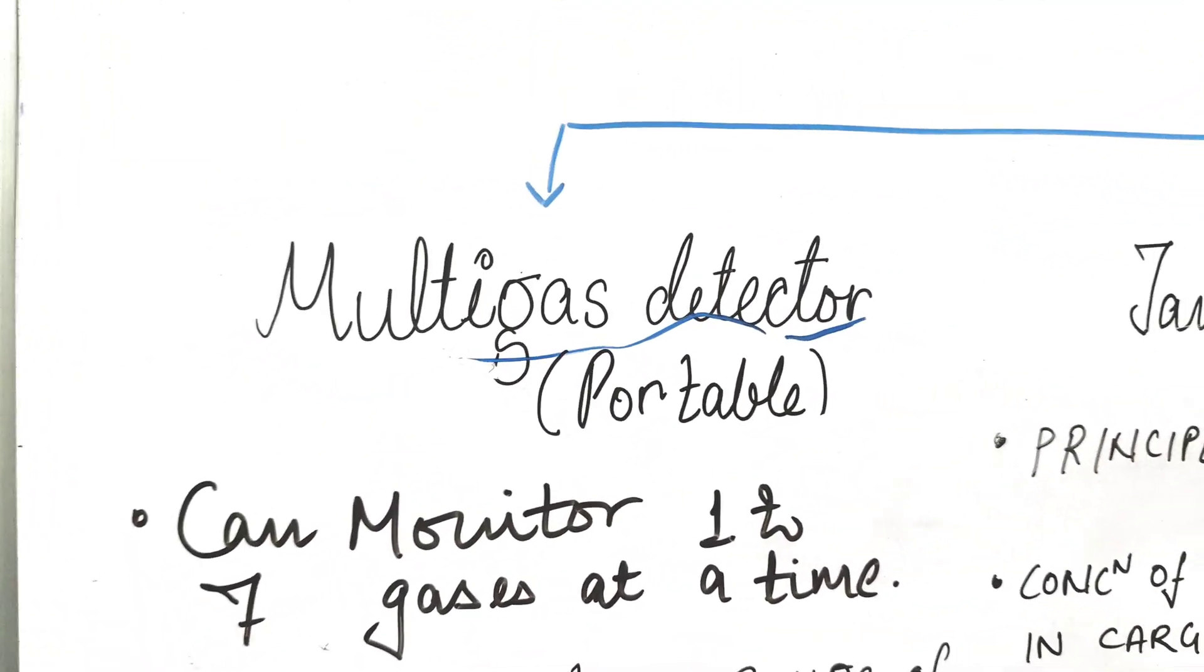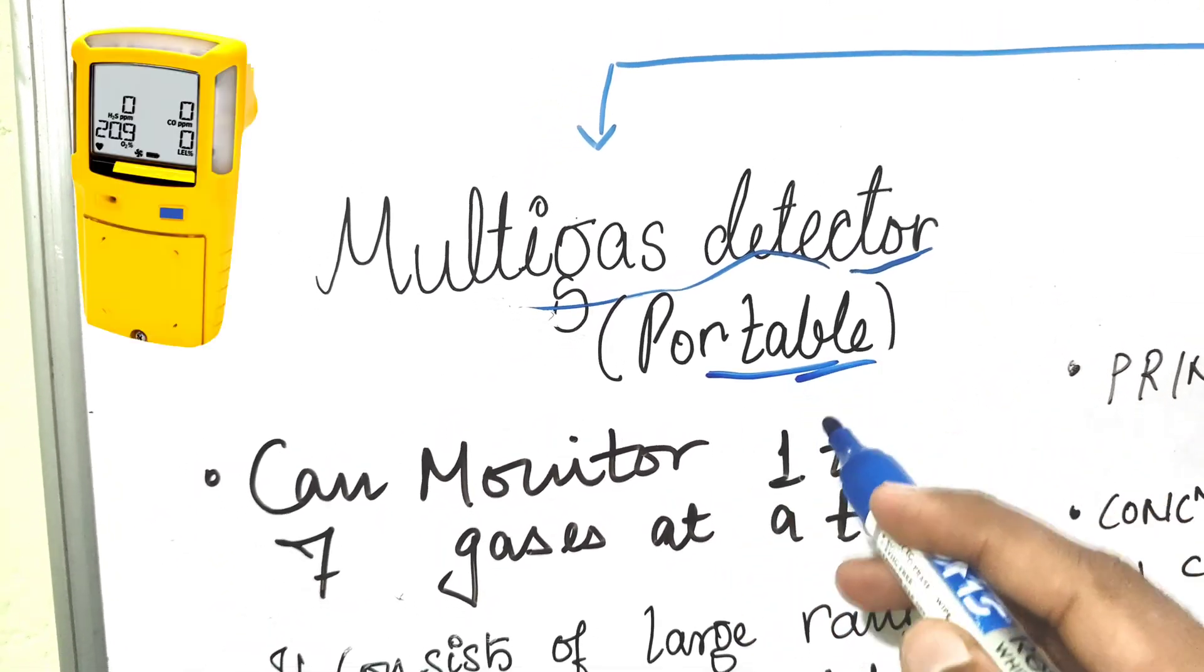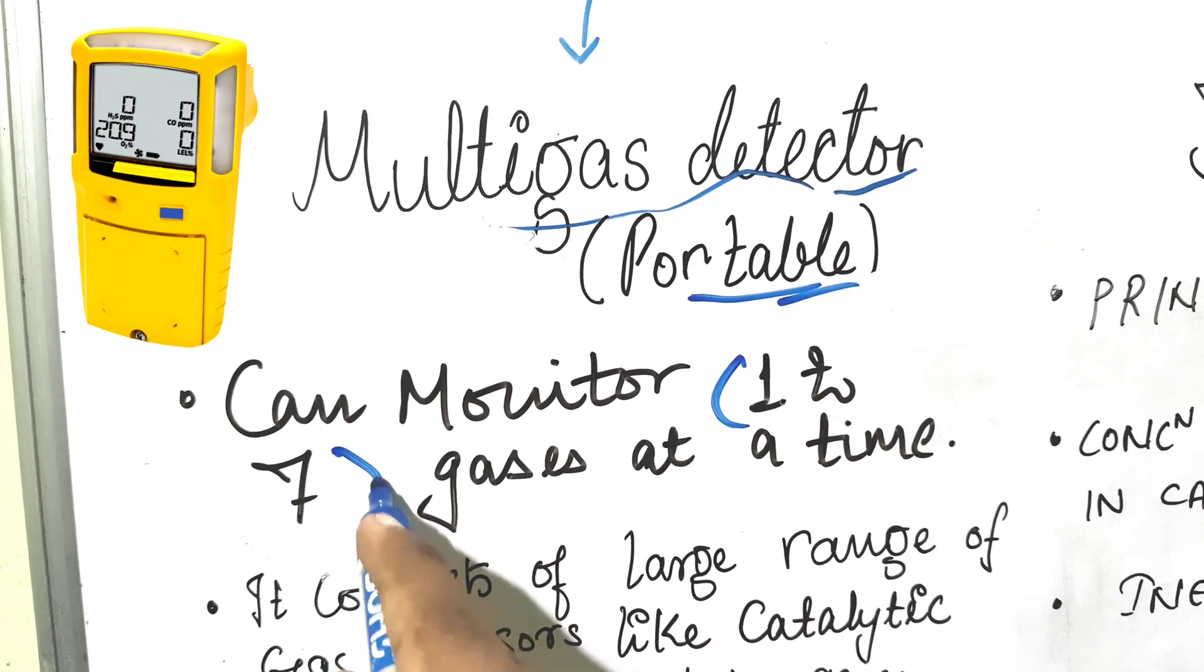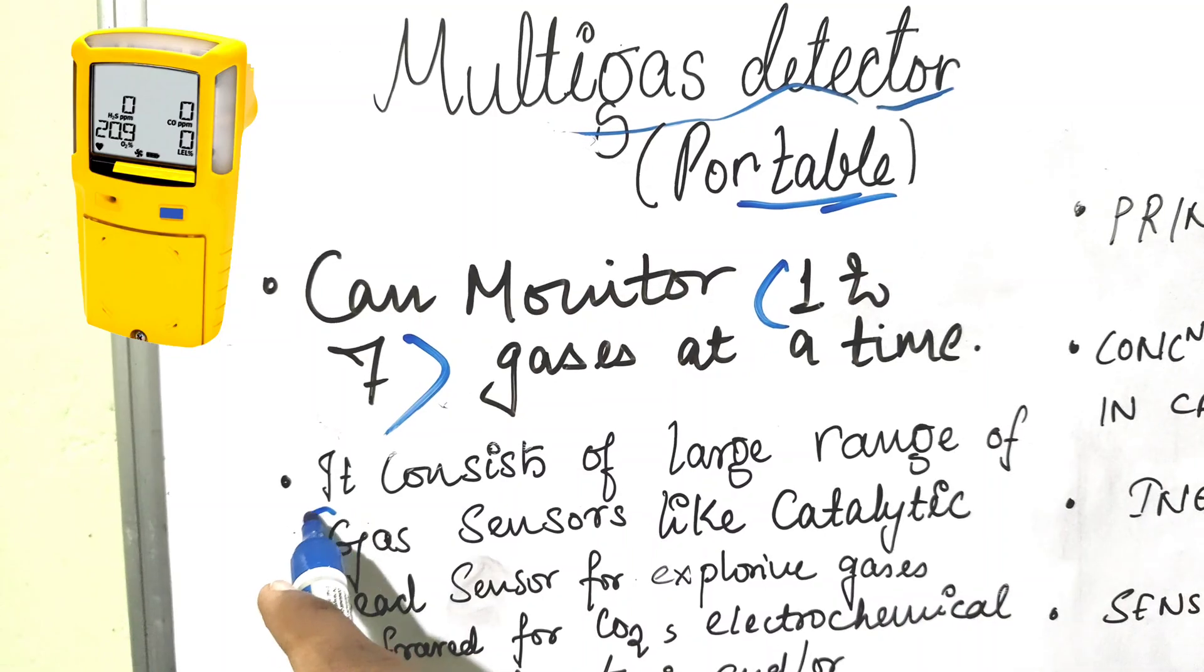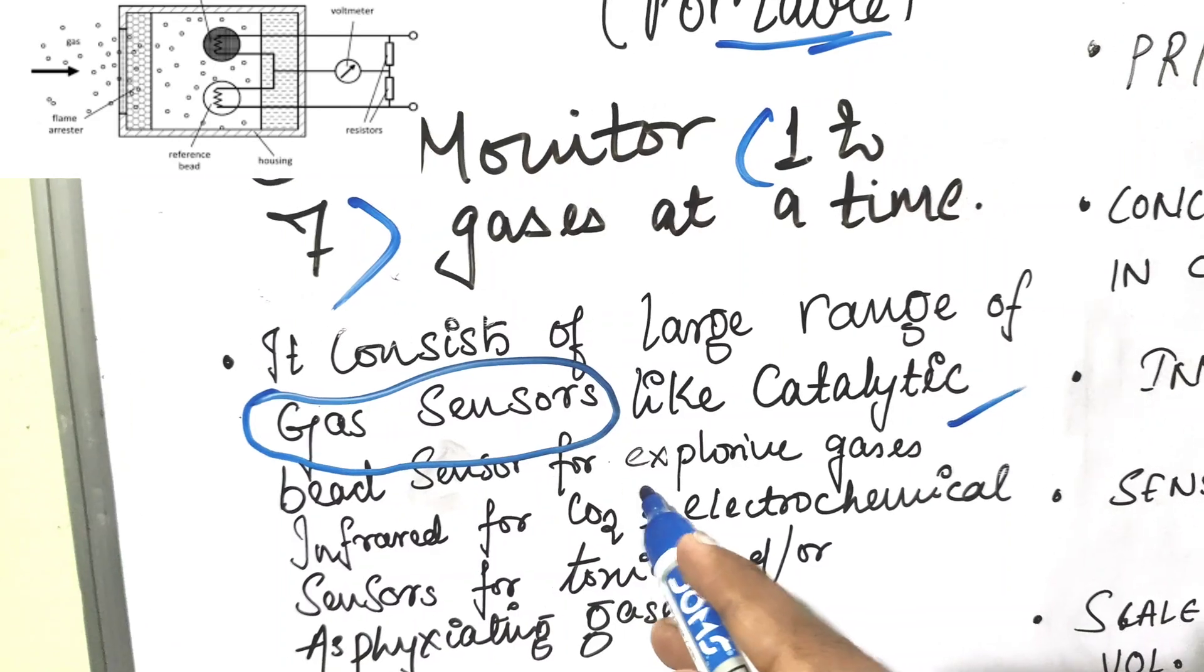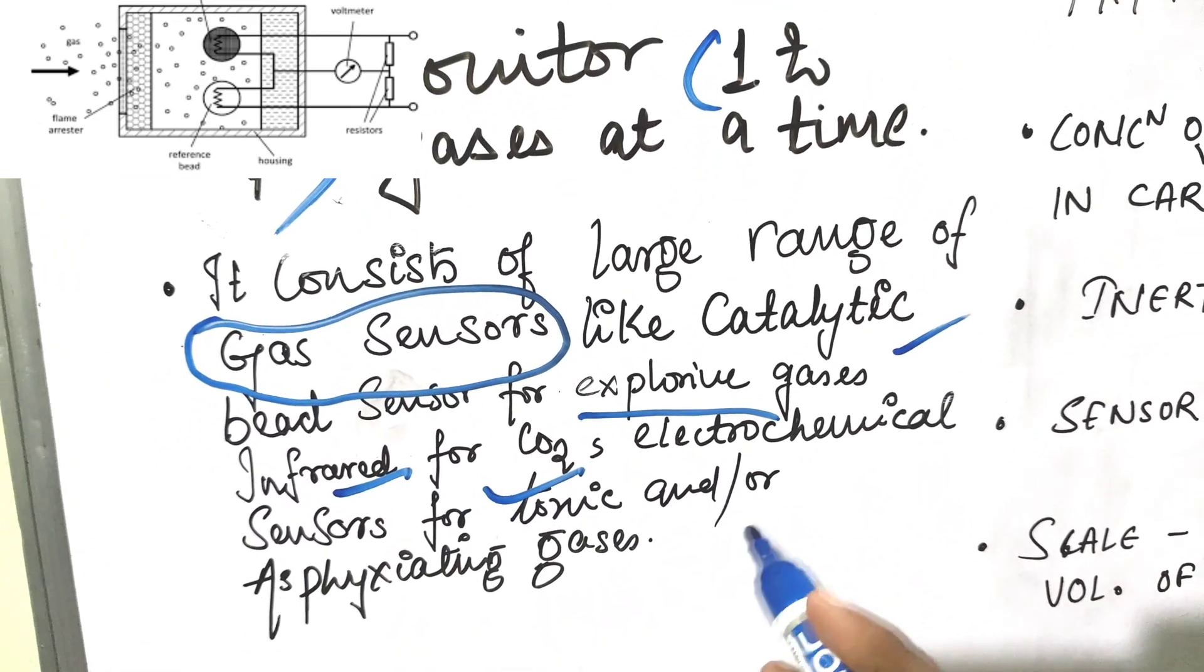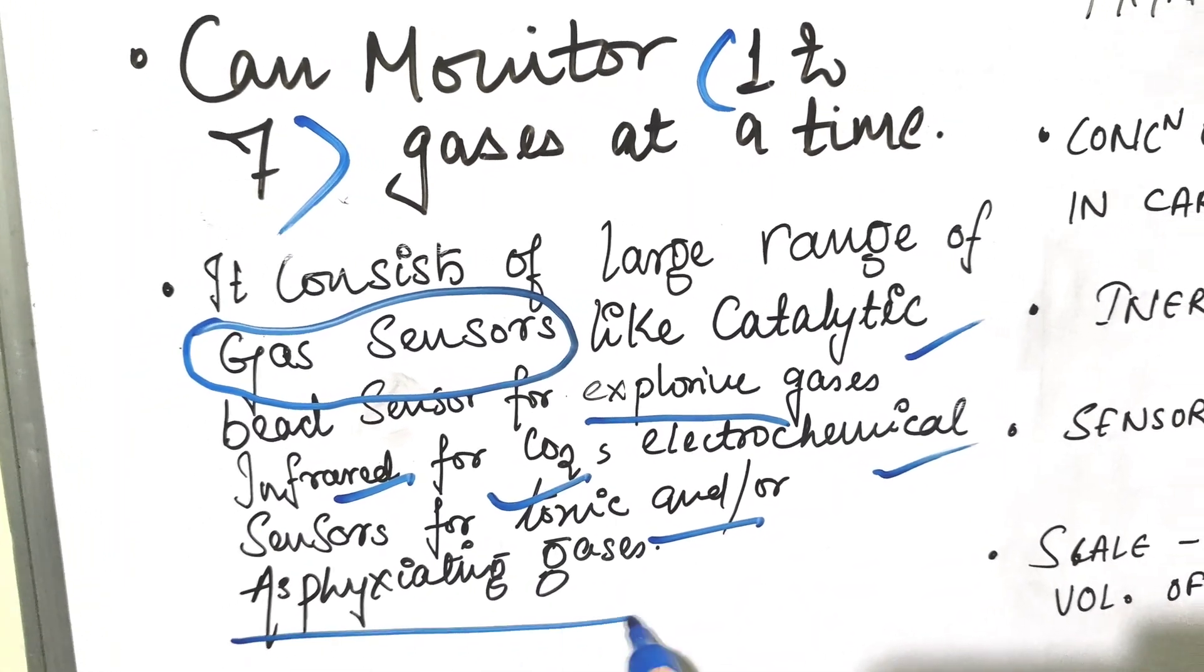First one is the multi-gas detector. This is a portable type. It can monitor one to seven gases at a time and consists of a large range of gas sensors like catalytic bead sensor for explosive gases, infrared for CO2, and electrochemical sensors for toxic or asphyxiating gases.